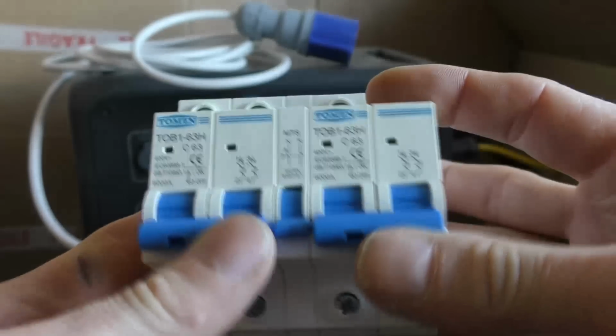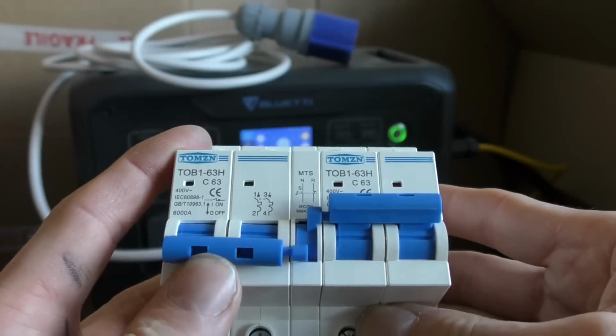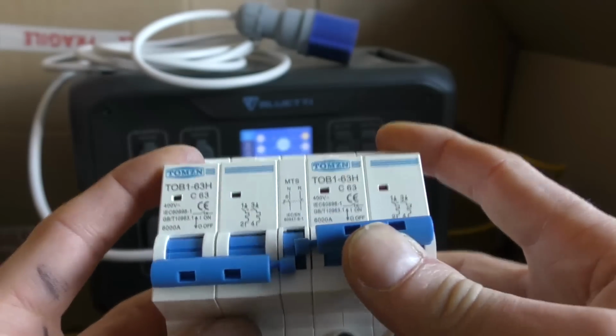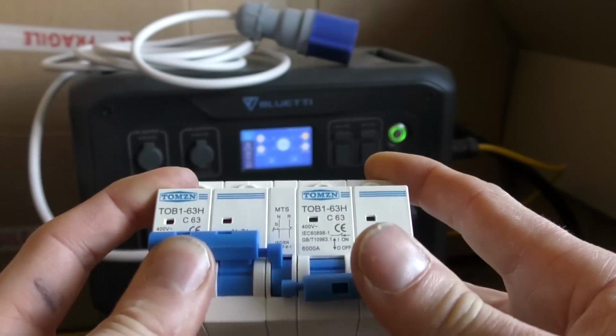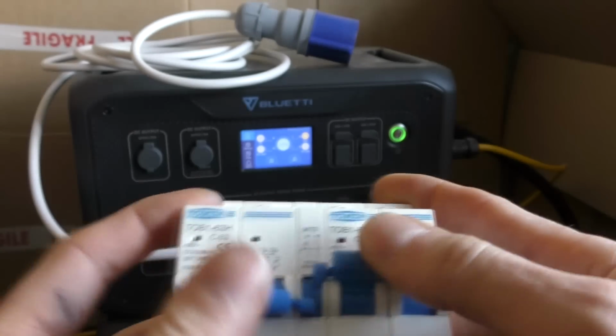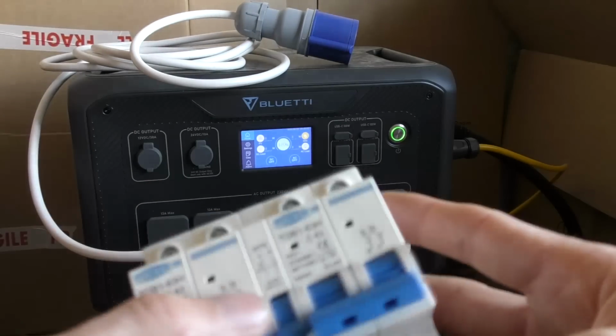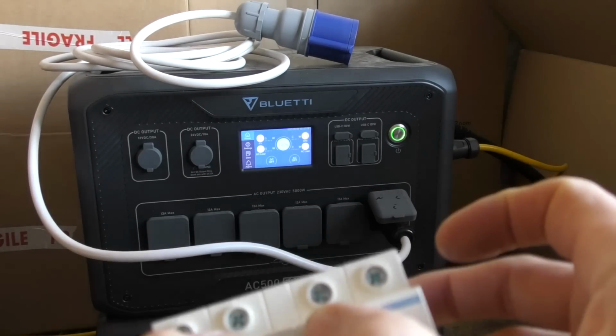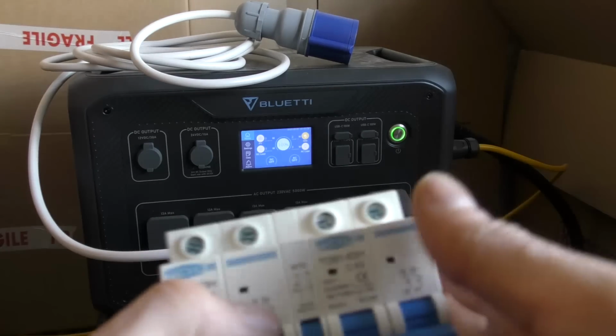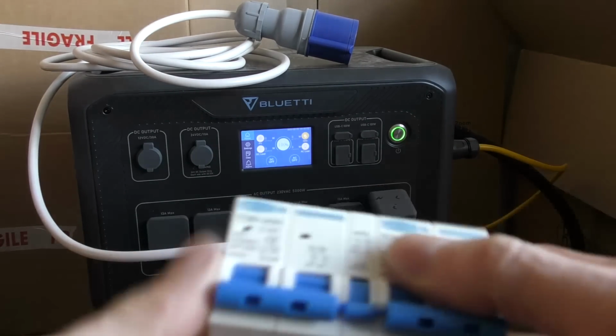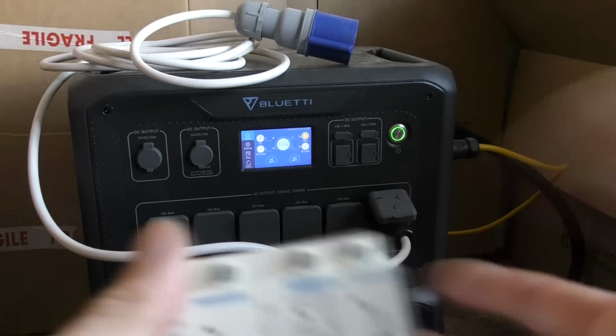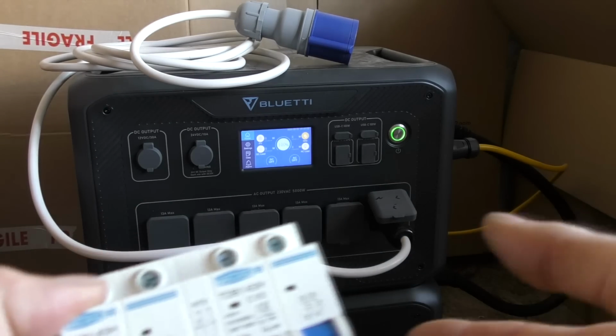This is basically a dual 63 amp breaker, which is interlocked, so only one side can be on at a time, it trips the other one. When the other one's turned on, you can't hold it. Even if you try holding it, it still trips out. So this would be a reasonable solution. Problem with this is, because this is effectively two independent devices, you'd have to bus the two inputs together. Also, it's got this half-width section for the interlock. Standard fuse boards are done in multiples of single units, so for example blanking plates and so on, so you'd end up with a half-width gap. So that's a possible solution, but it's only rated at 63 amps. This is a circuit breaker, not just an isolator, so if you're replacing an incoming 63 amp breaker in a situation, that might be a solution, but it doesn't really work for what I want to do.